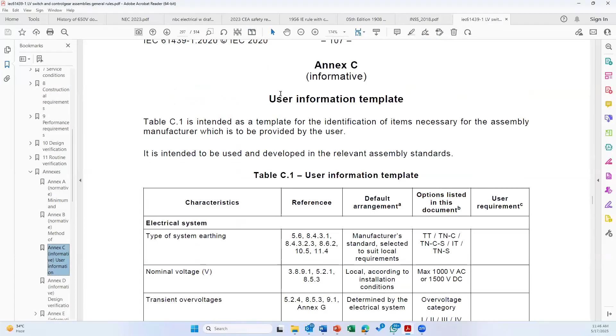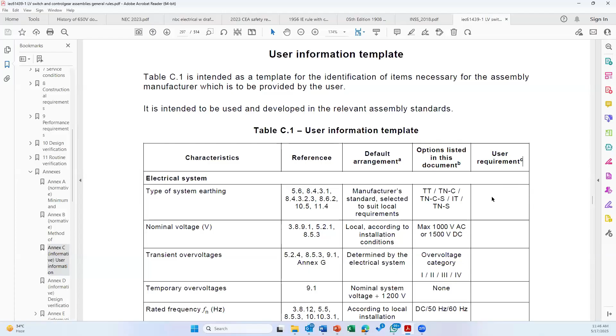Table C1 is intended as a template for the identification of items necessary for the assembly manufacturer, which is intended to be provided by the user. Means the customer who is going to buy this panel board, a switchgear or control gear assembly, has to make this information available. That means the designer, the electrical consultant, is supposed to fill up, you can see here, user requirement. He has to give this information to the panel builder so that the panel builder, the control gear supplier, can make the system useful.